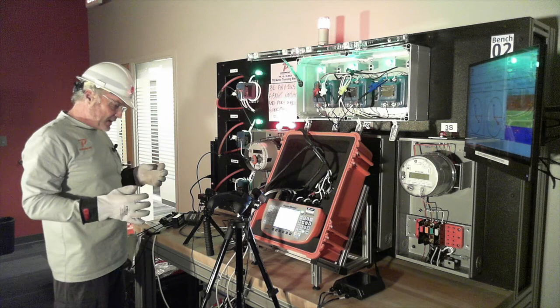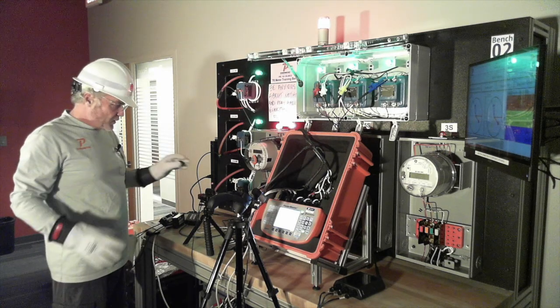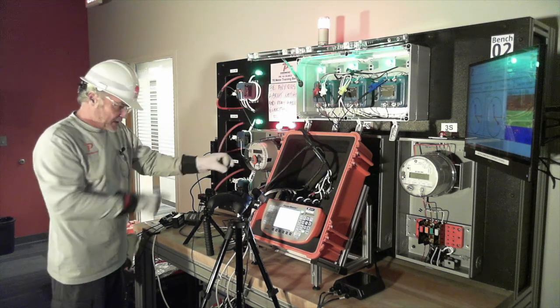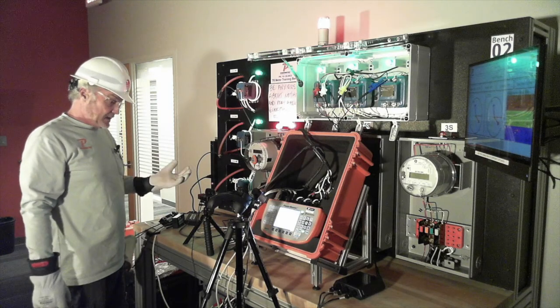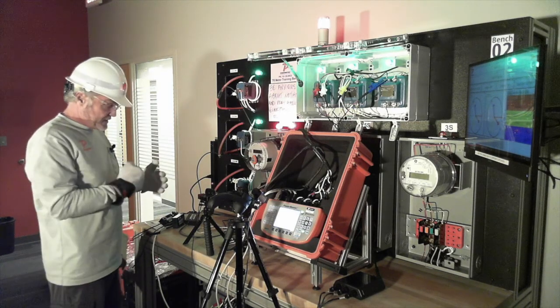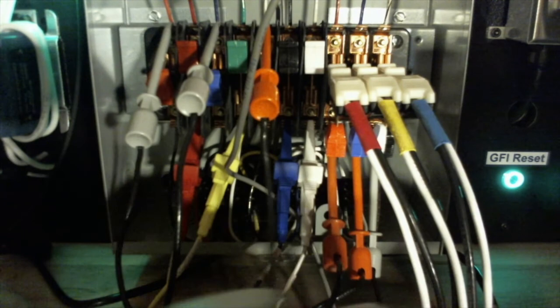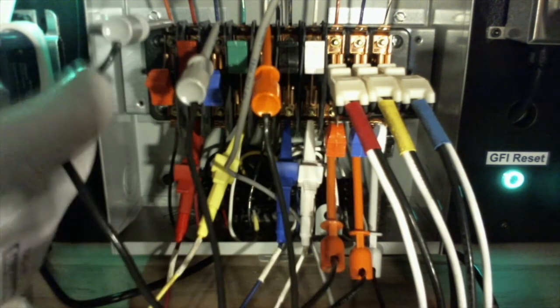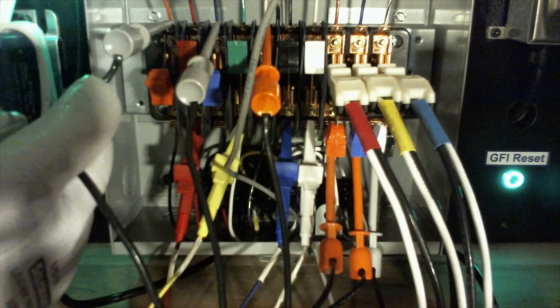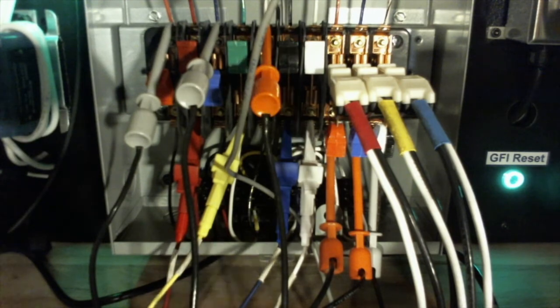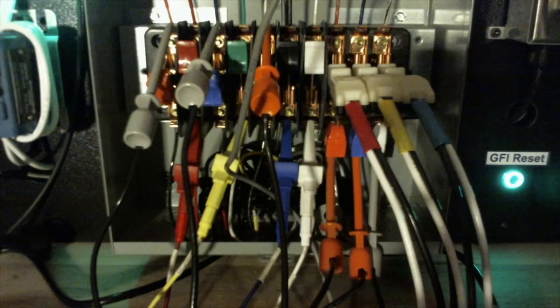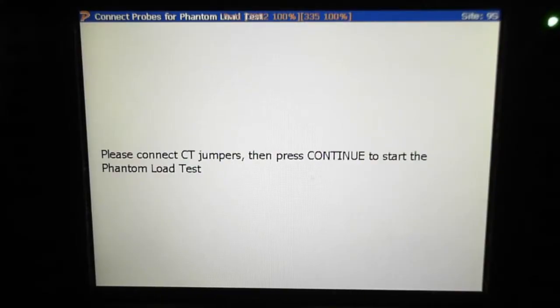This is the one I took a little more time with when I was first learning, because as we all know on this test switch, if I start making the wrong connections, that's when it can get a little dicey. So for safety's sake, go to the bottom of the long swing handle of the return on a phase, and on the same phase, go to the top of the short stroke shunt blade. Okay? So I'm going to hit continue.